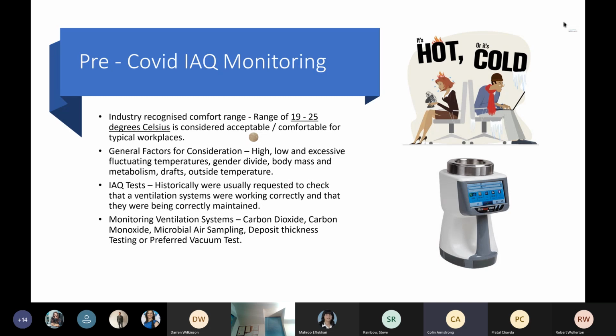We might have been asked to take a survey of a section of a system or a whole system, from the intake to the point of discharge located in an office, a classroom, or a restaurant, for example. This would typically include surveying the air handling units, the pre-filters, the coils, the bag filters, and the fan system, everything associated with that ductwork system. And then during that survey, they might request us to take deposit thickness tests, which Rob touched on, is an improved technique. I find that it's a really reliable and quantitative way of measuring the degree of cleanliness in ductwork, and it would determine when and how frequently cleaning is likely to be required.